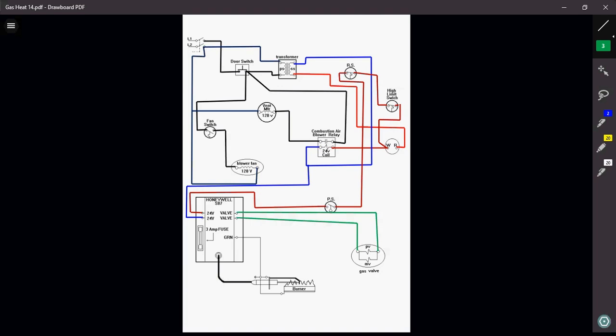But anyway, if it happens, it's an unsafe condition. That safety switch is going to open. Again, notice it's a temperature switch, a thermostat. It's going to open in the event of a sense of flame. It's going to pop. When it does, it's going to kill my ignition module. And when my ignition module can't receive a call, I'm not going to ignite my gas. I'm not going to energize the gas valve. Therefore, I'm not going to have any heat. The furnace is going to go into a lockout.